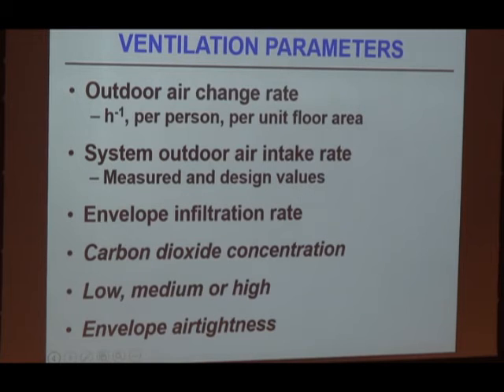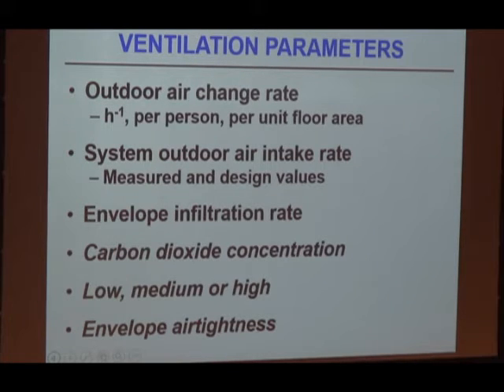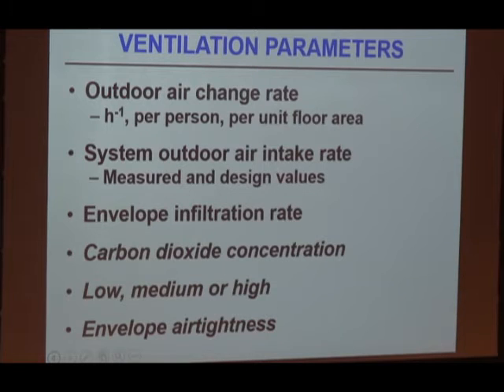Carbon dioxide concentrations in a ventilated space can be very informative — they're related to ventilation per occupant — but relating that to a ventilation rate is more complex than some people think. Qualitative descriptions like 'low rate' or 'high rate' are very subjective; a low rate in a hospital is a high rate in a home, so it's better to have a number. Envelope air tightness is also an important quantity to measure if you're trying to understand the ventilation characteristics of a building.